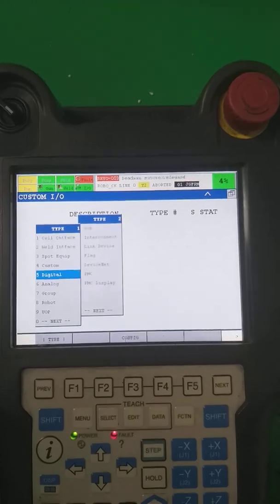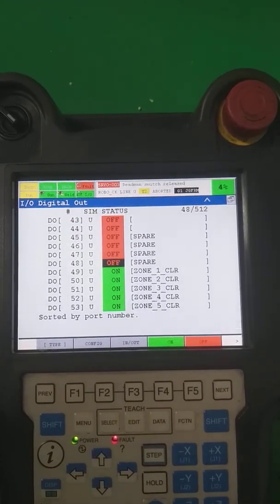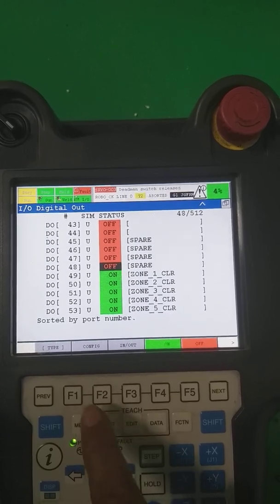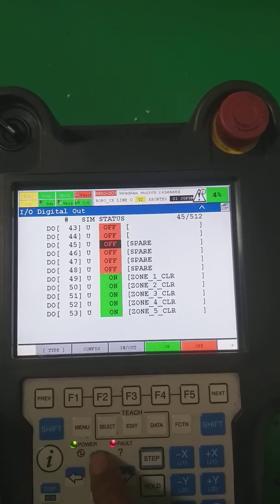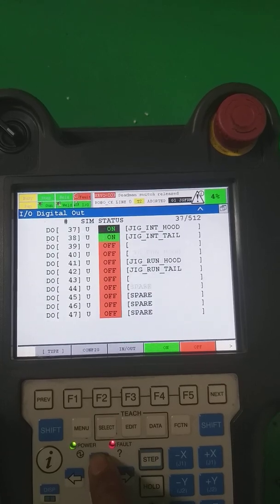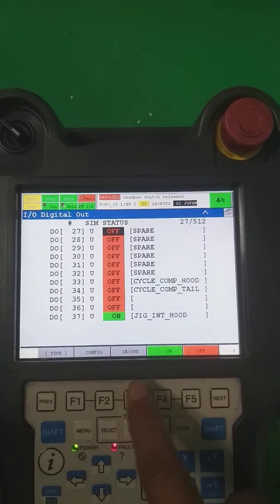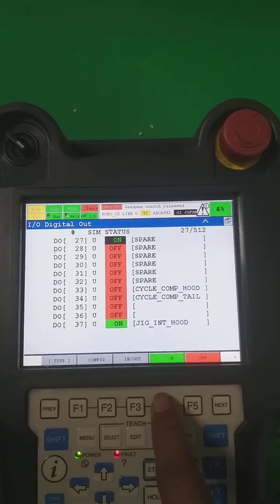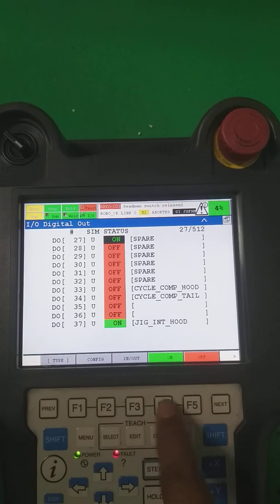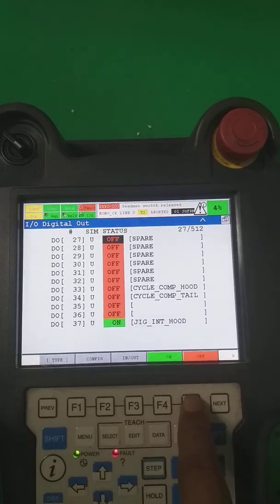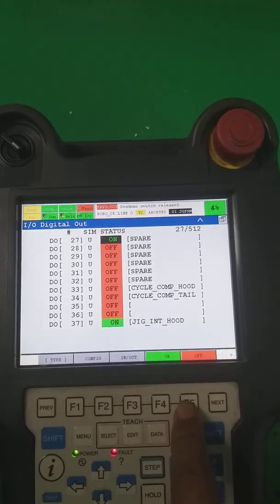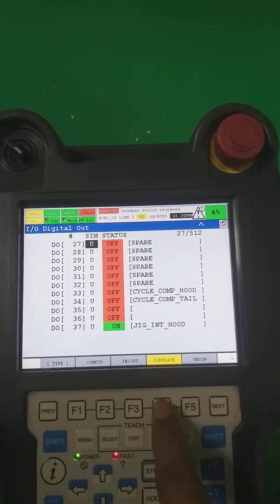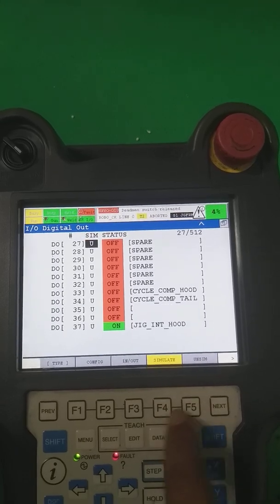Generally in practice, we use digital input/output for interfacing with PLC and other field devices. As you can see, the DO (digital output) numbers are 43, 45, 46 — they start from 1 and go up to 512. Here you have the option to manually turn them on/off during input/output testing. You can check if they are going on or off with the field device.